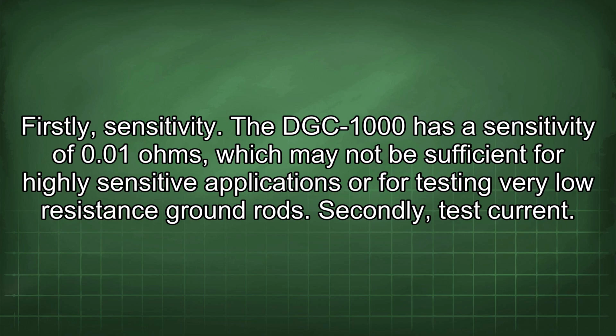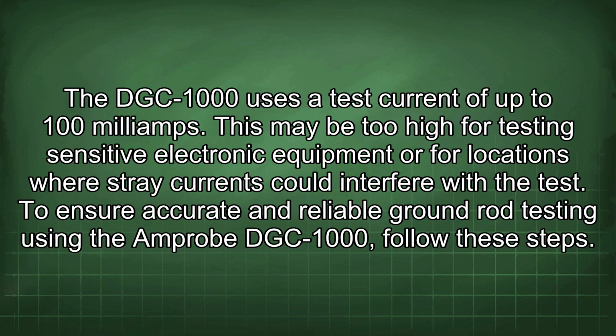Secondly, test current. The DGC-1000 uses a test current of up to 100 milliamps. This may be too high for testing sensitive electronic equipment or for locations where stray currents could interfere with the test. To ensure accurate and reliable ground rod testing using the Amprobe DGC-1000, follow these steps.